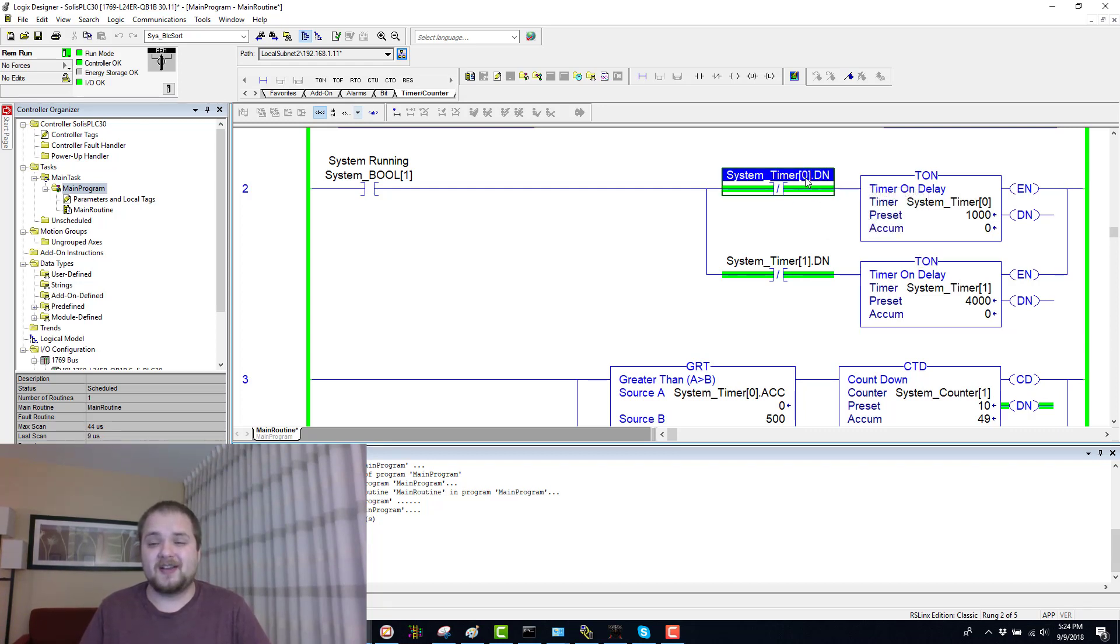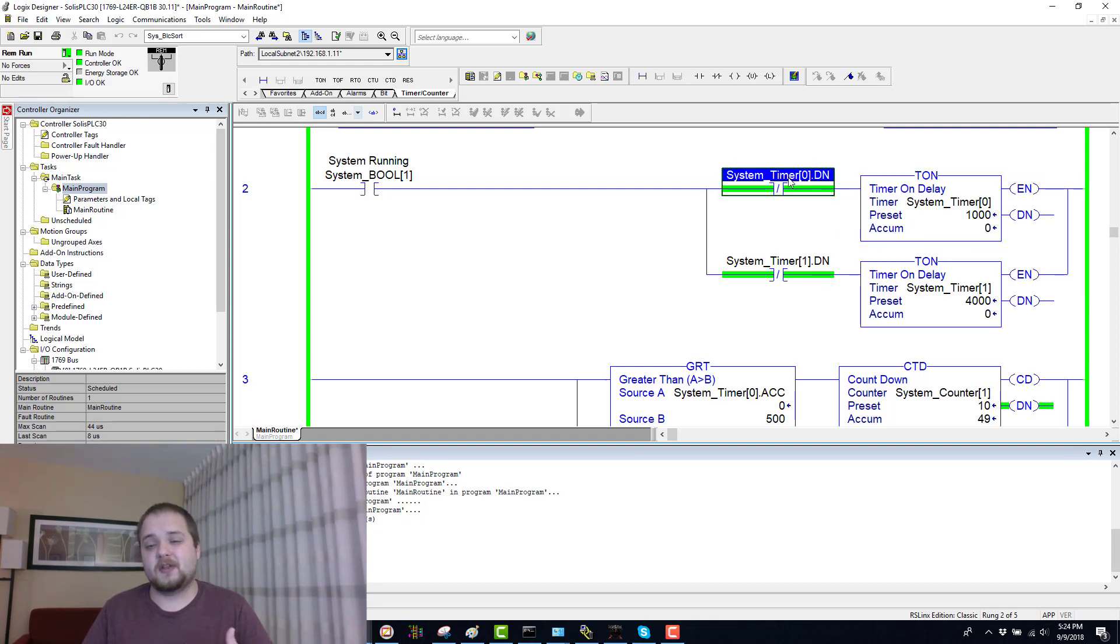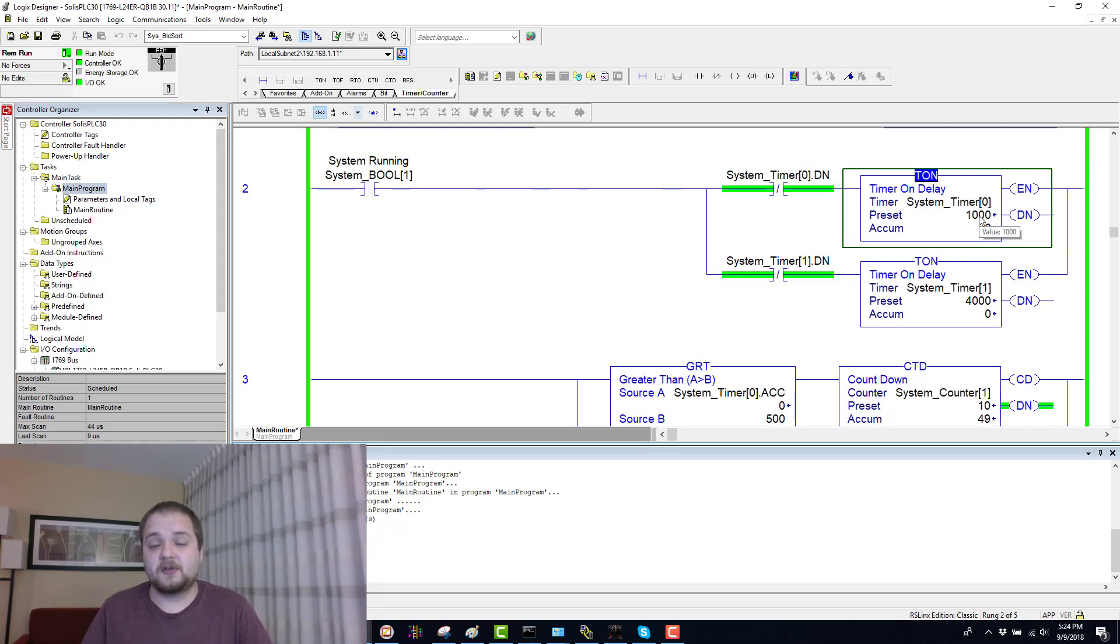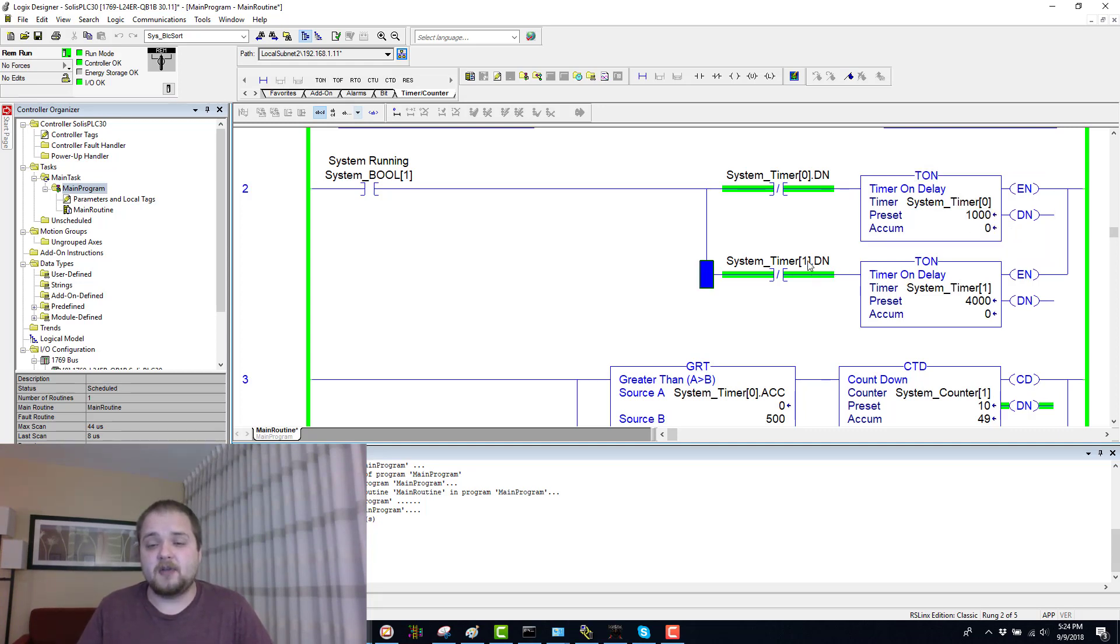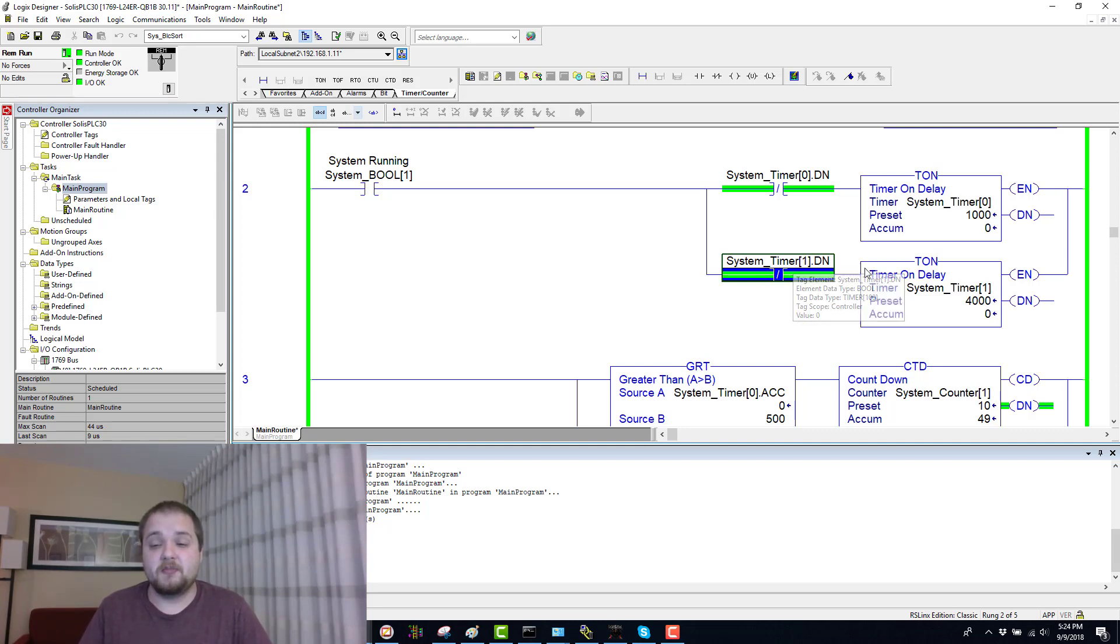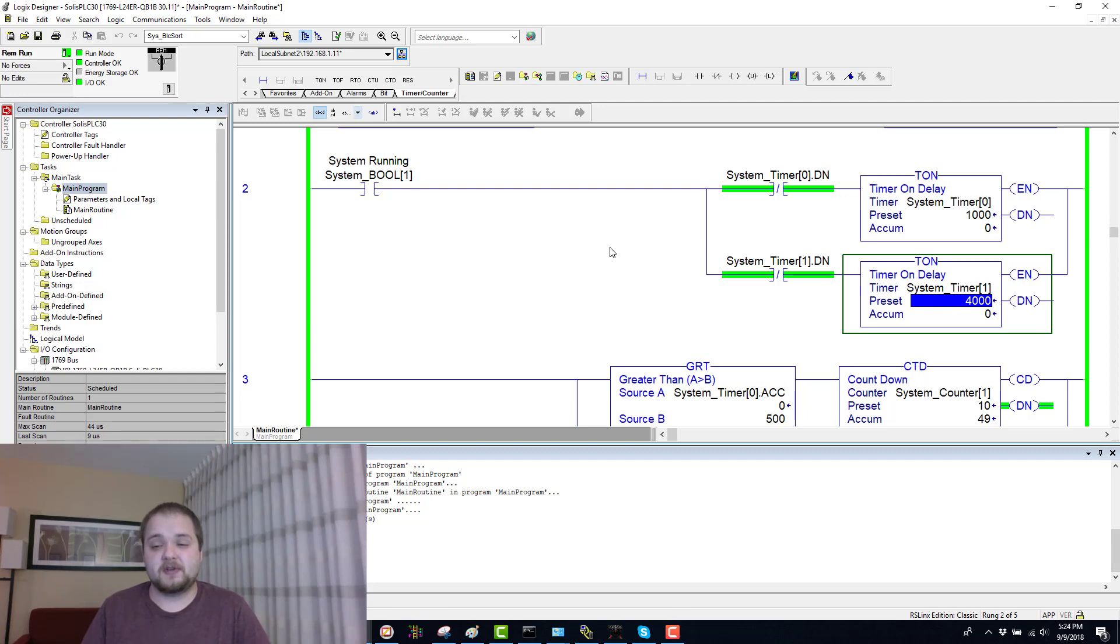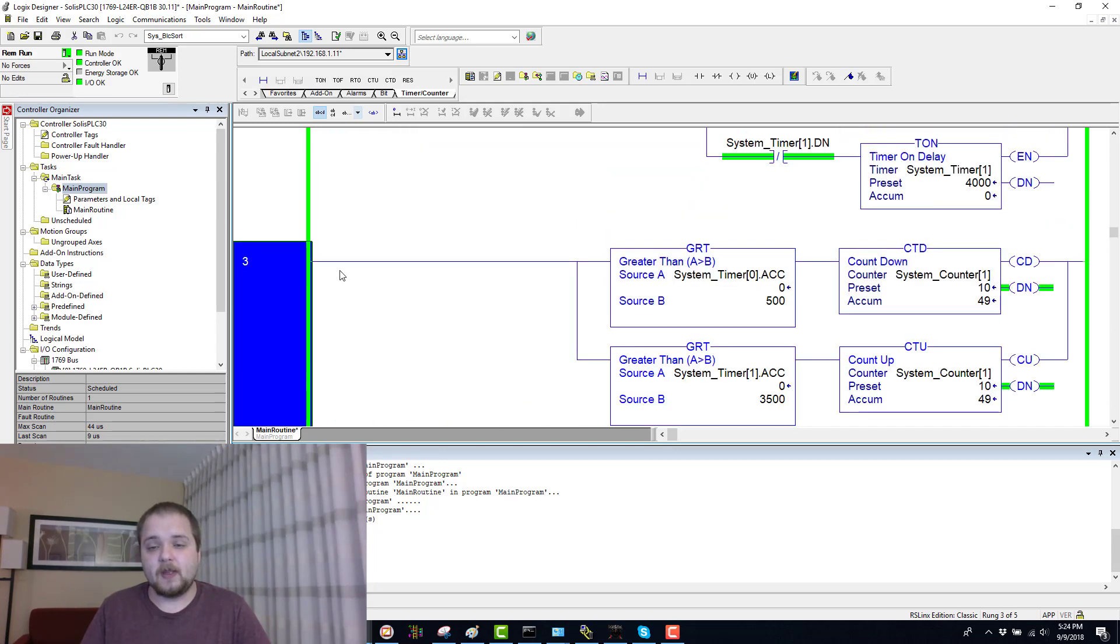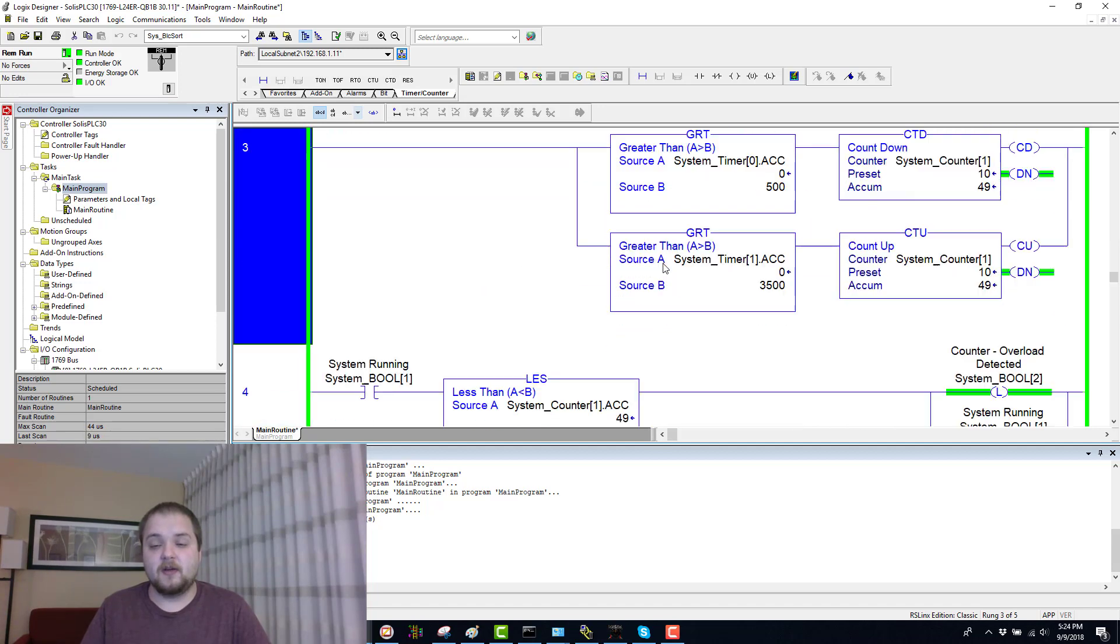In the first branch, as long as the timer is not done, which is of course a condition which tells you that the timer will continuously run, if everything is true then it will count up to a thousand, which translates to a single second in the real world. Do remember that the timers are in milliseconds. You have a separate System_Timer1 which is also going to be on its own not done bit, and that's going to be counting up to four seconds in real time or four thousand milliseconds.